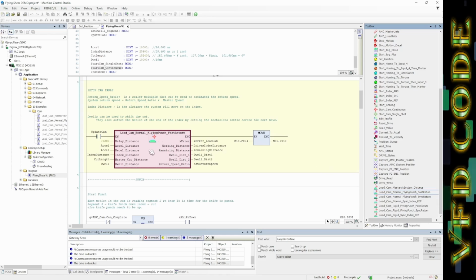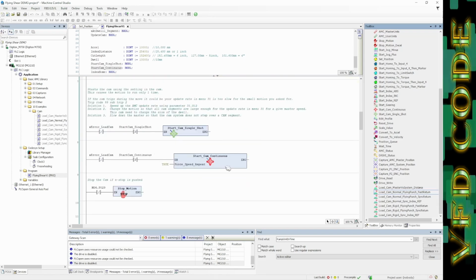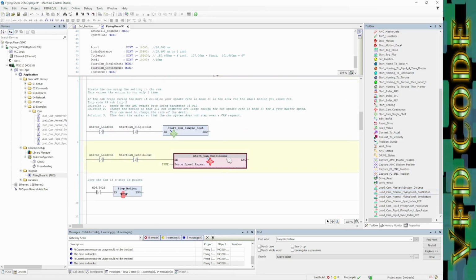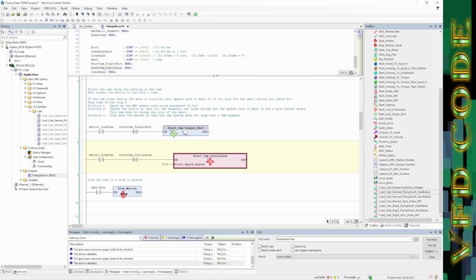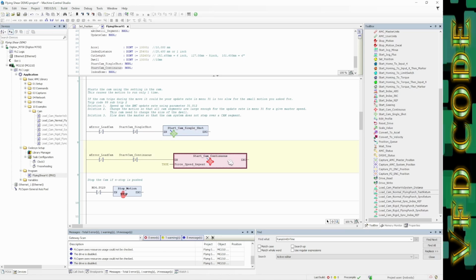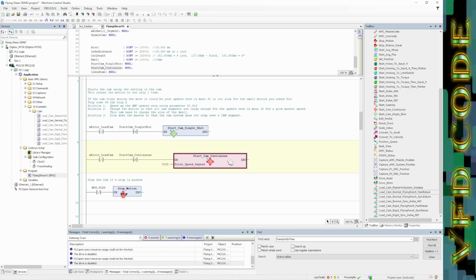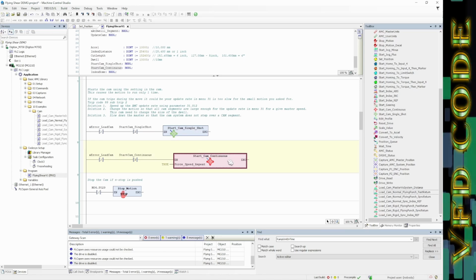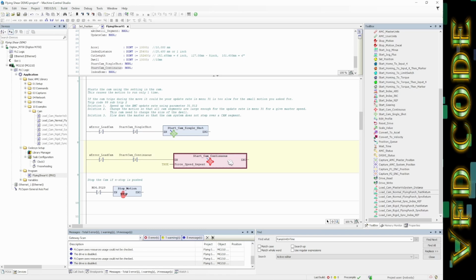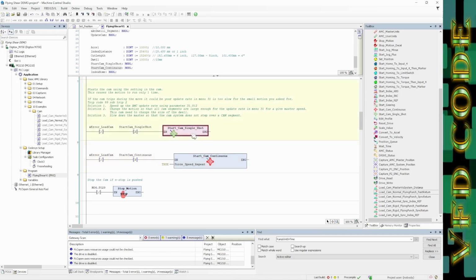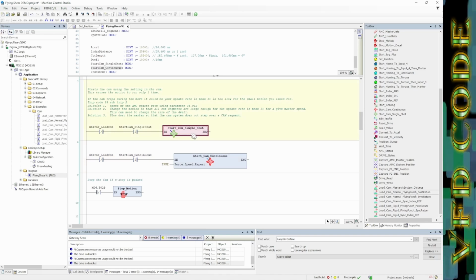And we also need to be able to start and stop this block. So the other blocks you're going to need are Start Cam Continuous and Start Cam Single Shot. Now, what this one does is basically cause the cam to repeat over and over again, just like our demo's been doing today, cutting over and over. But if we wanted to cut it only one time, just a single cut, we could do this and it would just make a single cut.